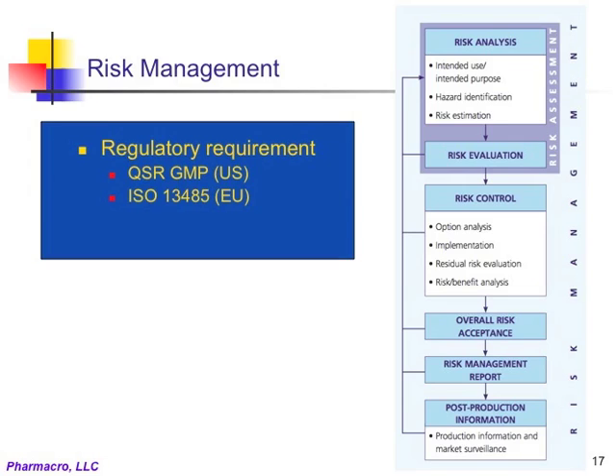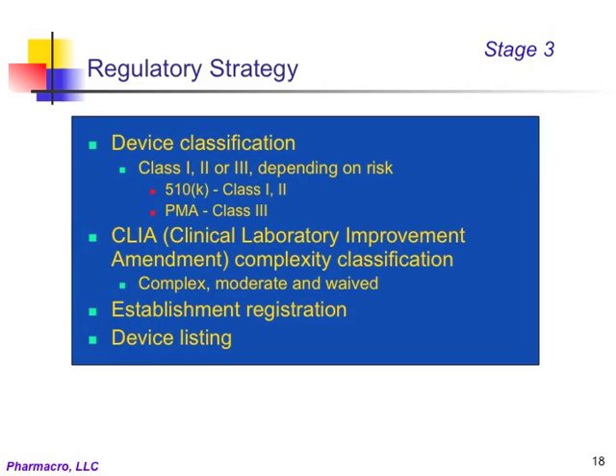Risk management essentially consists of risk analysis in the form we have just discussed, followed by implementation of risk mitigation and the assessment of residual risk to ensure that the residual risk is acceptable. This is then documented in the risk management report, and subsequently any changes to the device, process, package or label are evaluated with respect to their effect on the risk profile, and the changes are implemented only if the residual risk is acceptable. Another part of the product development activity is the regulatory strategy.